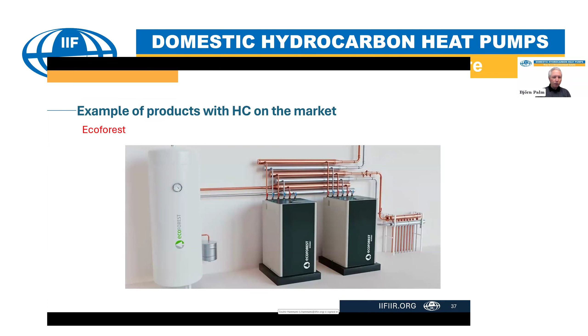And if you remember one of the slides of Daniel, you could see that if we have a charge of 150 grams of propane, then there are no restrictions on the size of the room where this heat pump should be placed. It's like a refrigerator—you don't have to consider where it should be put. So in this design, there is no ventilated enclosure, no propane sensor. There are two plate heat exchangers. There's no internal heat exchanger or desuperheater in this case. And of course, the COP of this system is 4.3 at these conditions you see here.